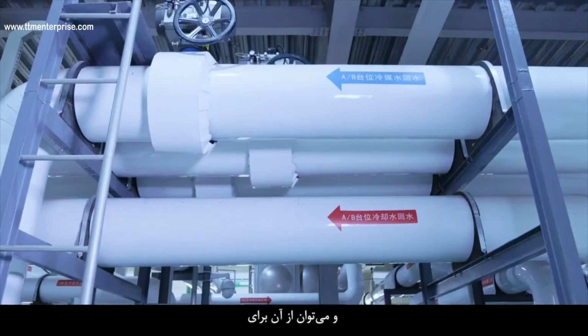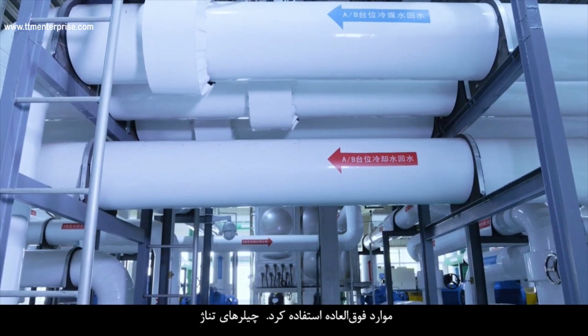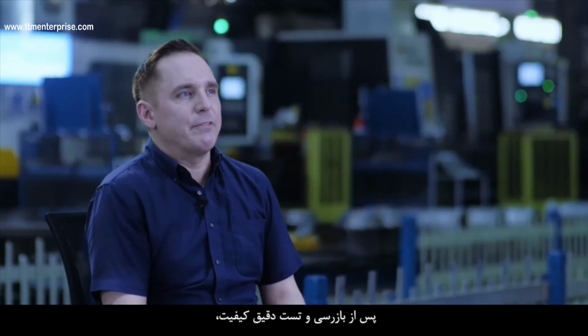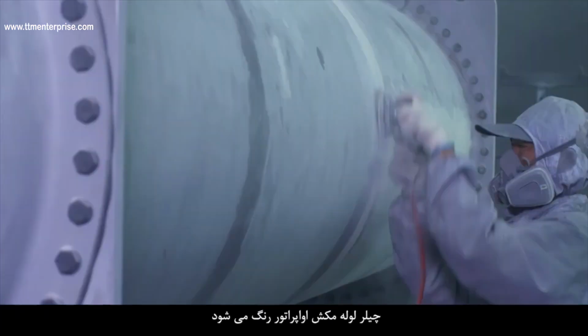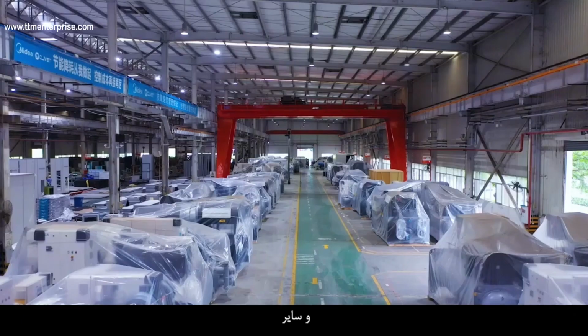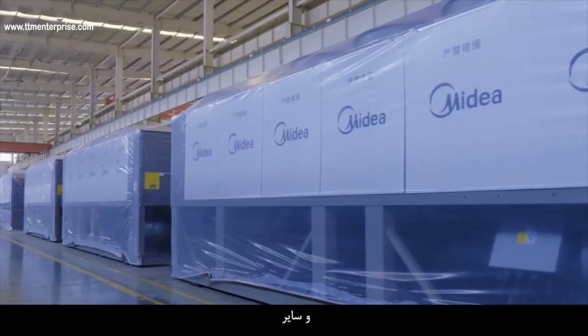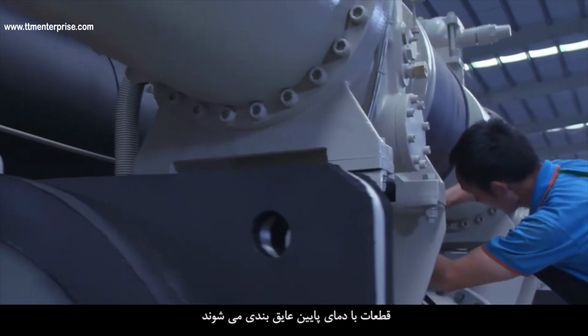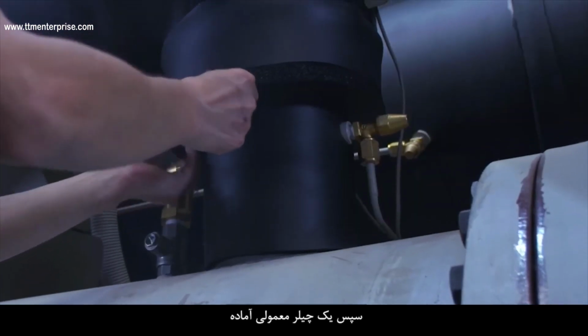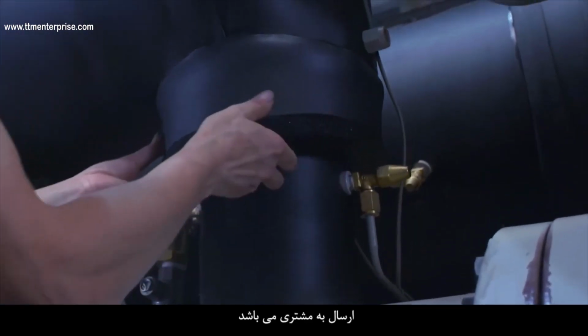This chiller laboratory, with a testing capacity of up to 4,000 RT, adopts industry-leading measurement and control technologies. It can be used for super large tonnage chillers. After strict quality inspection and testing, the chiller will be painted. The evaporator, suction pipe, and other low-temperature parts will be insulated. Then, the centrifugal chiller is ready for shipment and delivery to the customer.